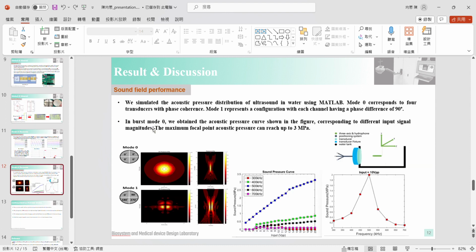In the sound field, we simulate the acoustic pressure distribution of the ultrasound in water using MATLAB. Mode 0 corresponds to 4 transducers with phase coherence, and Mode 1 represents a configuration with each channel having a phase difference of 90 degrees. In burst mode 0, we obtain the acoustic pressure curve shown in the figure, corresponding to the different input signal magnitudes. The maximum focal point acoustic pressure can reach up to 3 megapascals.